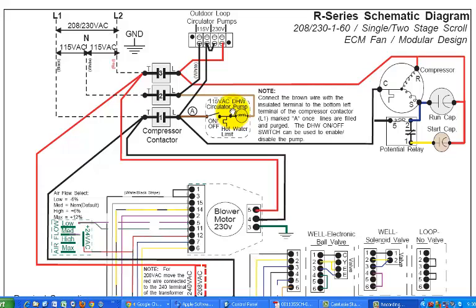And so once again, at the risk of overstating it, oh yes, pardon me, I should back up and say we also might want to run a pump or whatever at 115 volts. Well, there again, if we come up to this point off L1 and come from the neutral to this terminal, now we've got 115 volts between those 2 points, and we can run any accessory that requires 115 volts and also should run when the compressor is running off those 2 terminal points. That covers then the right-hand side, if we want to call it that, of the compressor contactor. If we go back over to the left-hand side for a minute, you'll notice that there are a couple of connection points that are happening here, and those are going to be sending power down to a couple of other components.